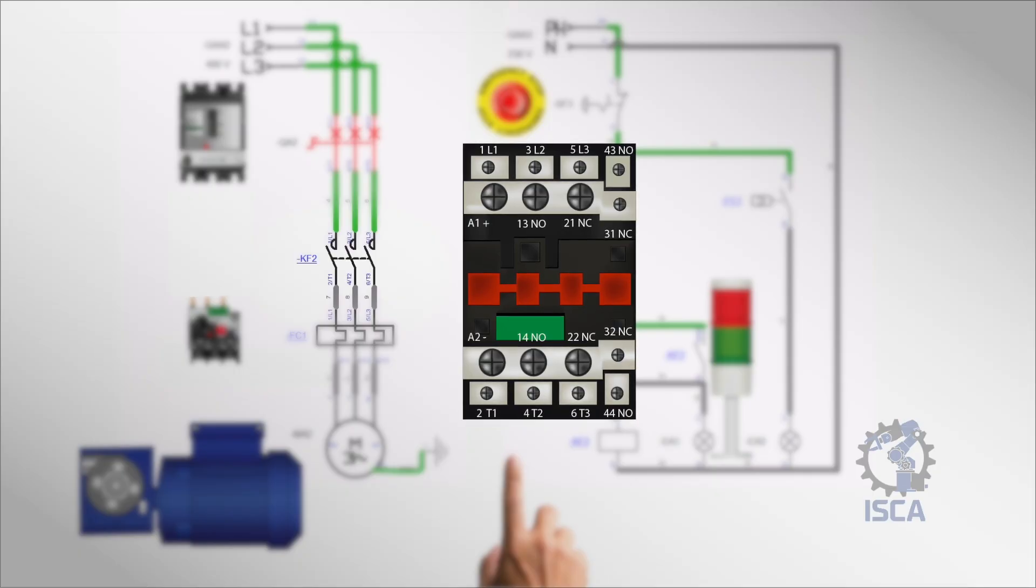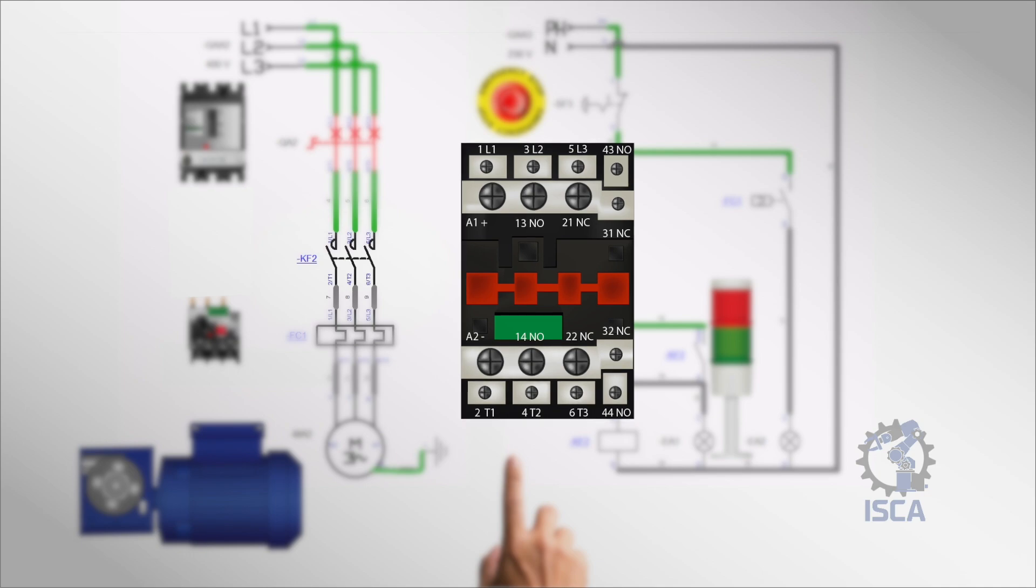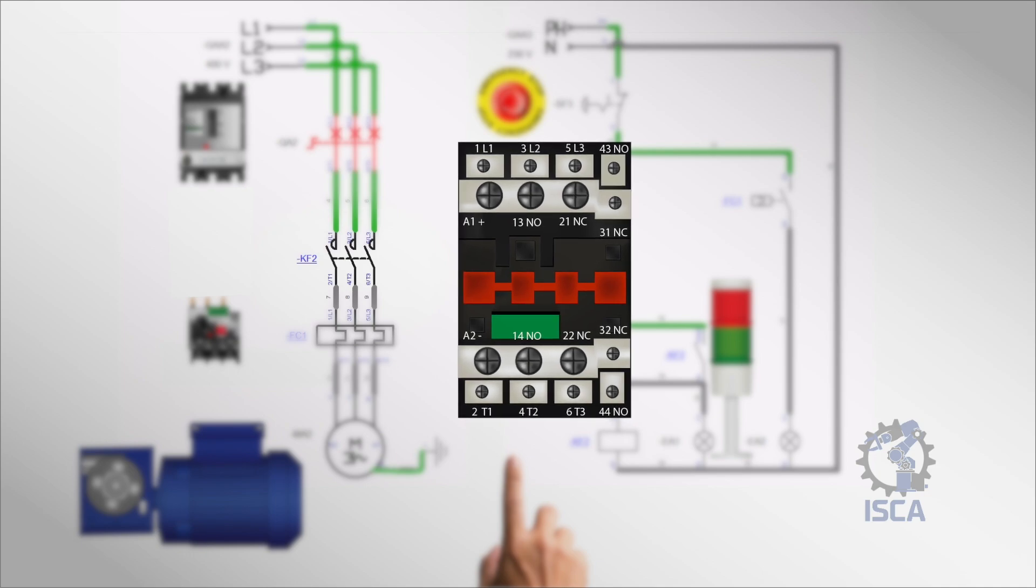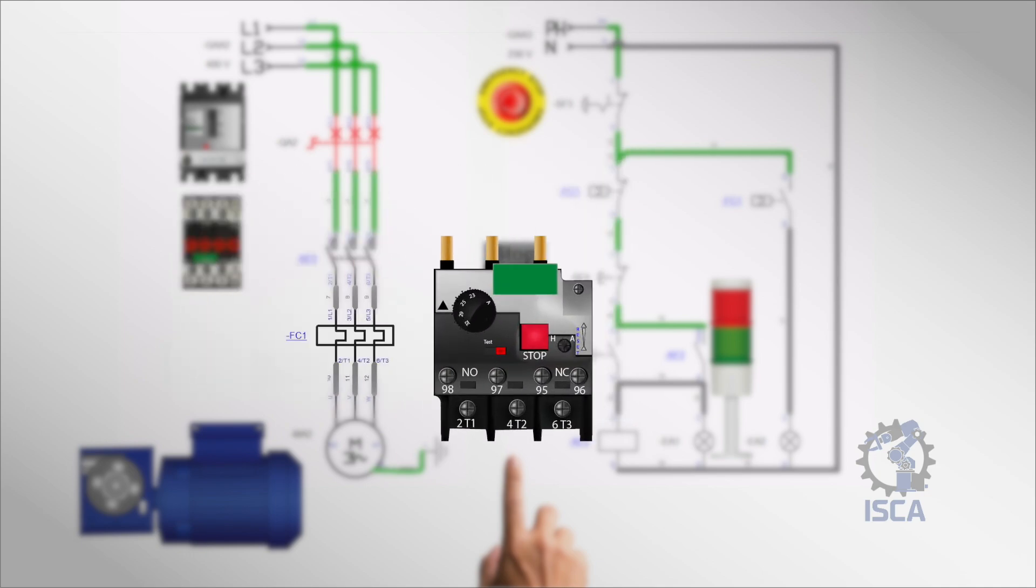Overload relay: this device protects the motor from damage caused by excessive current draw. It monitors the current flowing to the motor and trips if it exceeds a preset limit for a specific duration. Unlike the circuit breaker, which protects against short circuits and severe overloads, the overload relay is tuned to protect against less severe but prolonged overcurrent conditions that can cause motor overheating.